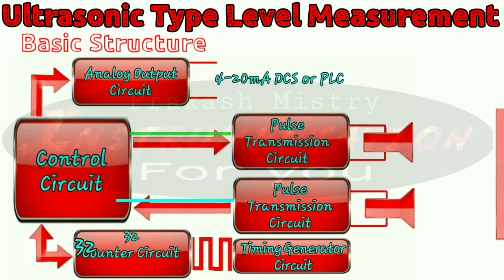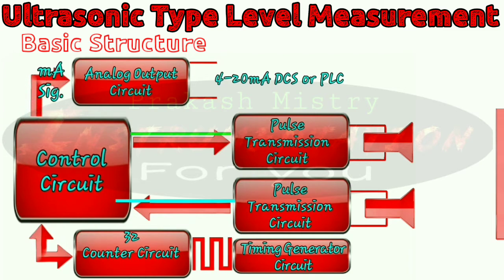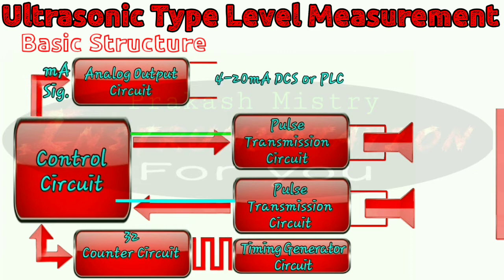This time delay is proportional to the level of the product. If the time delay is short, then the level is high; if the time delay is high, the level of the tank is low. The level is finally converted to a 4 to 20 mA signal. A 4 mA signal indicates 0% level and a 20 mA signal indicates 100% level. This 4 to 20 mA output signal carries the level data and can be transmitted over a long distance to process control devices such as DCS or PLC.